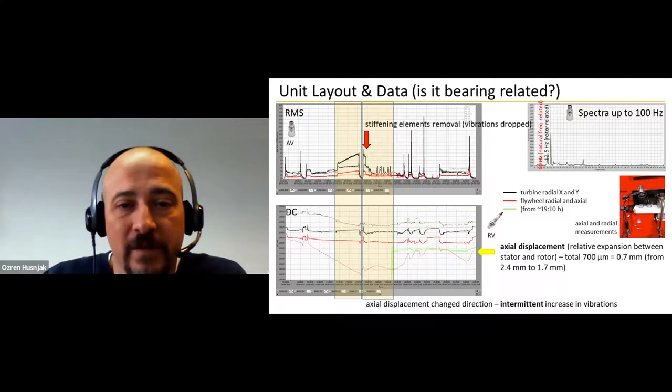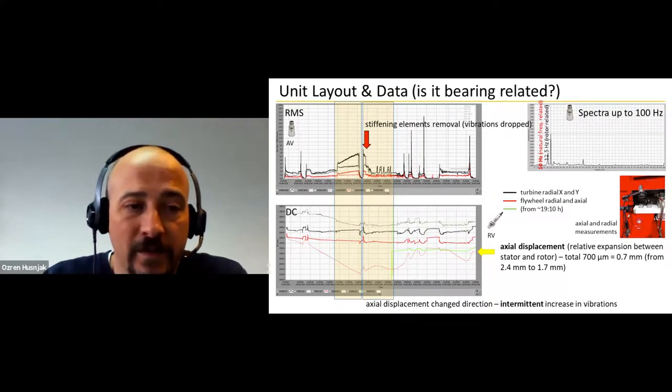And these graphs, the upper graphs, show you trends of measurement data, basically the RMS value of the vibration levels from the accelerometers. There were several startups and rundowns that you can see. I've squared the interesting portions, which we'll analyze in a bit more detail. One is here, where with temperature at the same regime, the vibrations increased suddenly without obvious cause, and then started increasing more and more. And this one is obviously temperature related, because after this jump, no other parameter was changed.